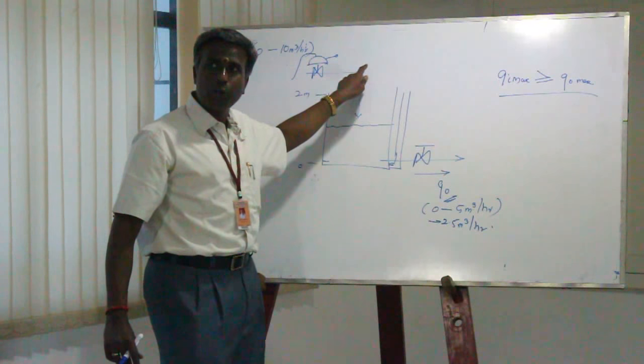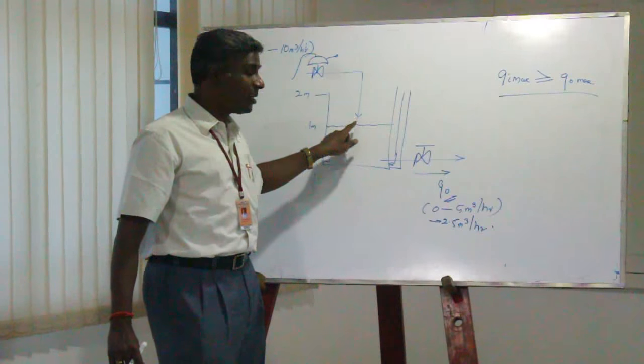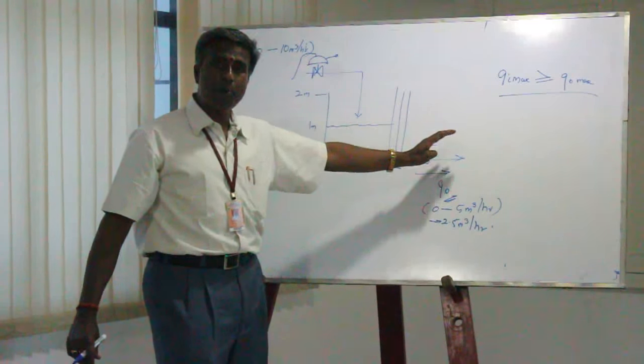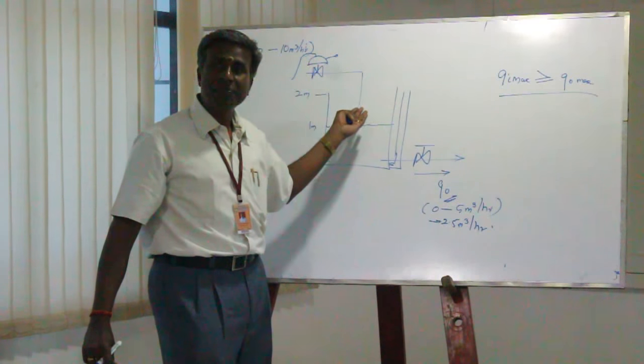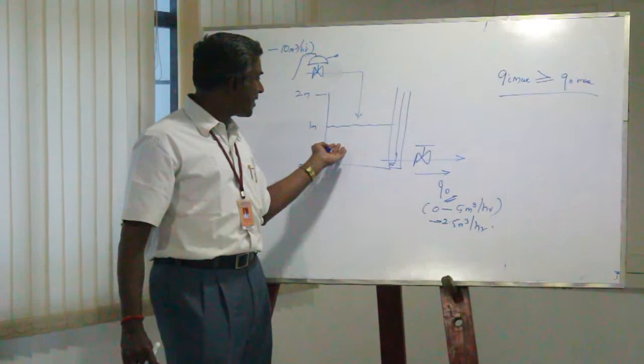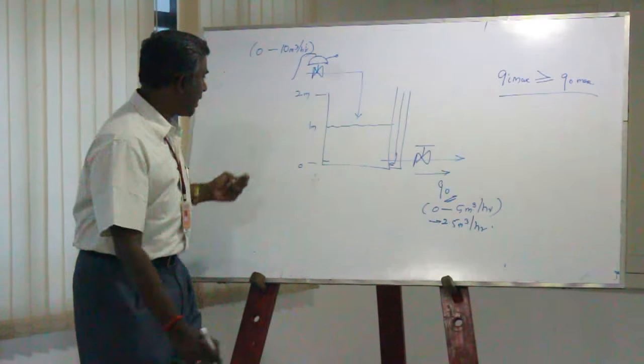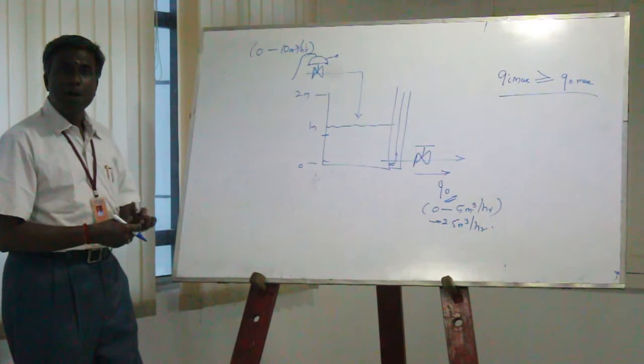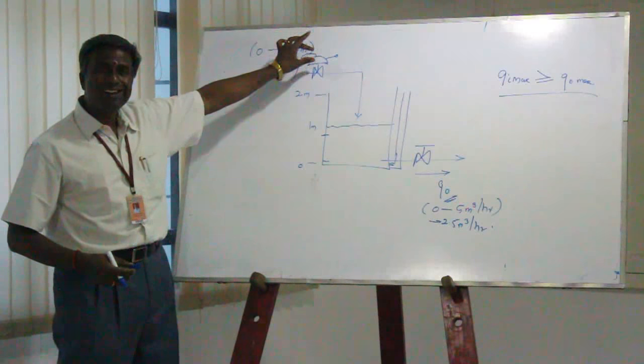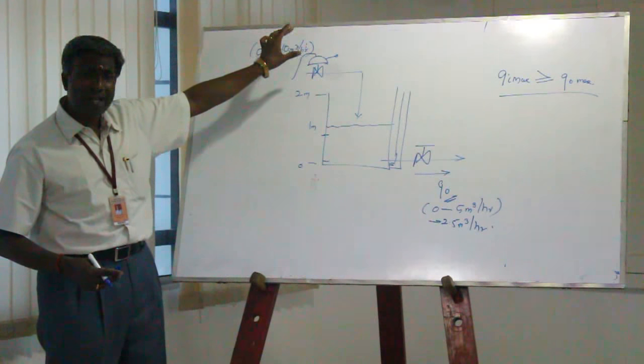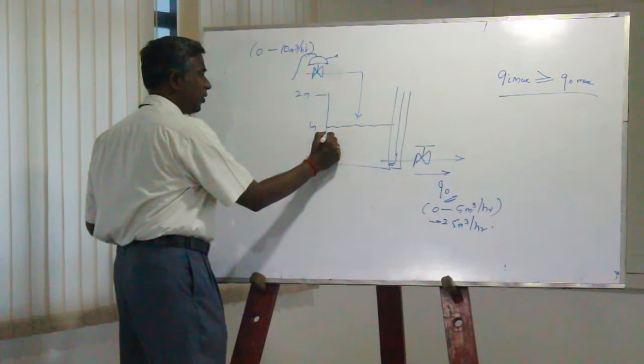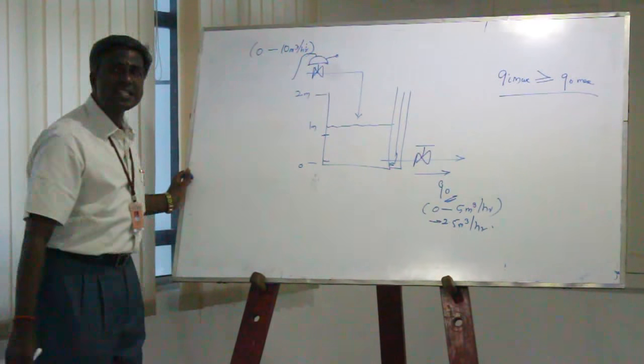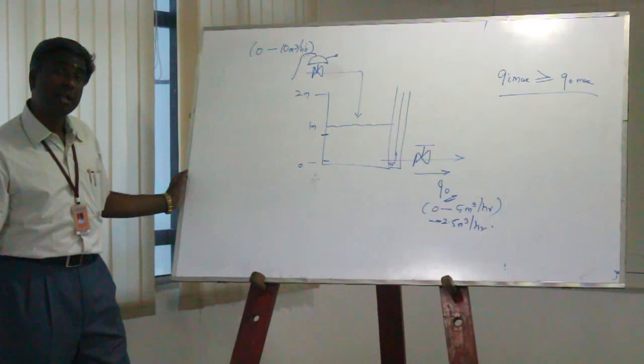When this is going to be 10 cubic meters per hour, obviously against an output of 2.5 cubic meters, the level will begin to increase. As the level is getting increased, when I am around this area of 0.8 or 0.9, probably I think of regulating this flow. When I try to regulate this, this particular value of level can go above that and then it can get settled.